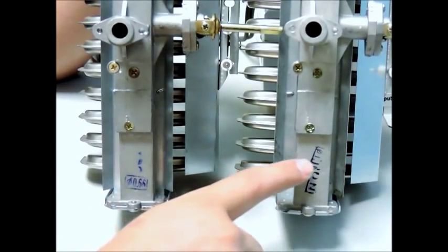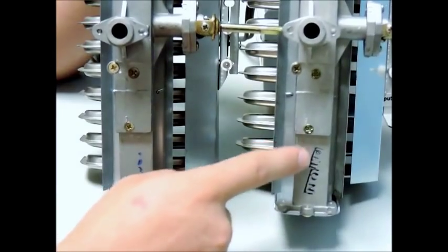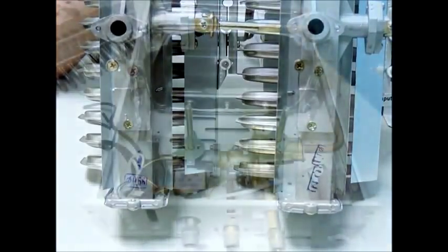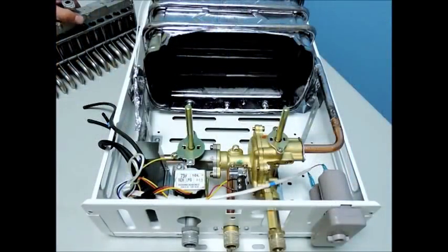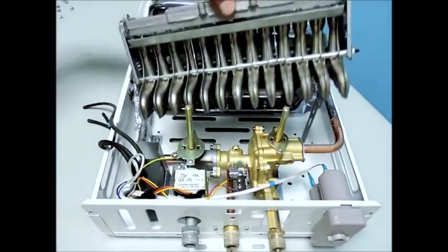Please note that your burner assemblies can be identified via a stamp on the bottom side of the assembly. The assembly with a 0.66 stamp is used for propane and the assembly with a 1.11 is used for natural gas. This way, you can identify the proper burner assembly in case you get them mixed up during this process.